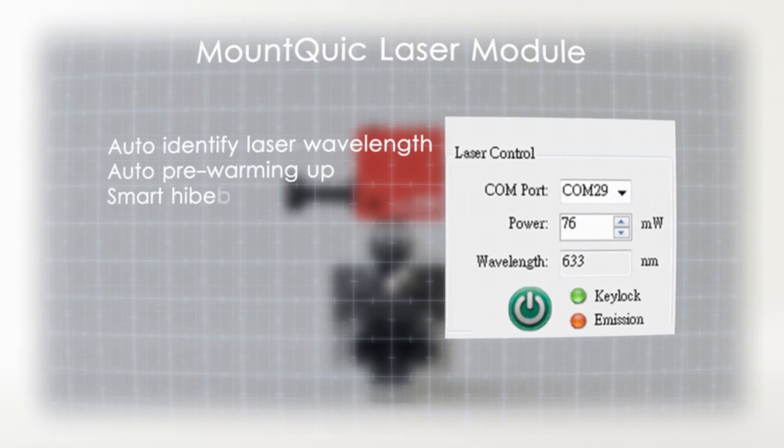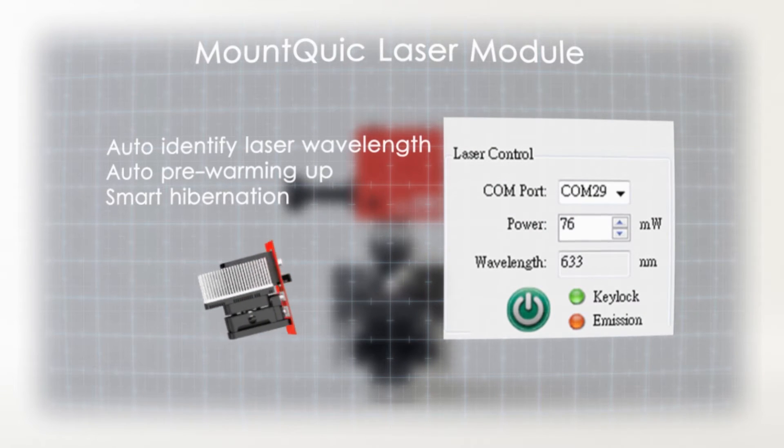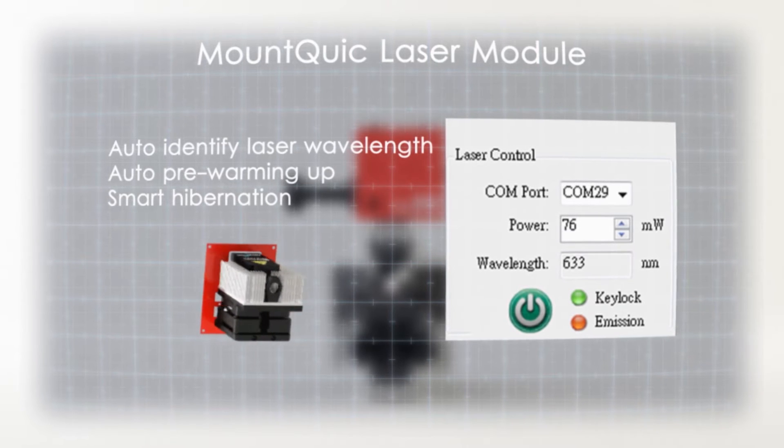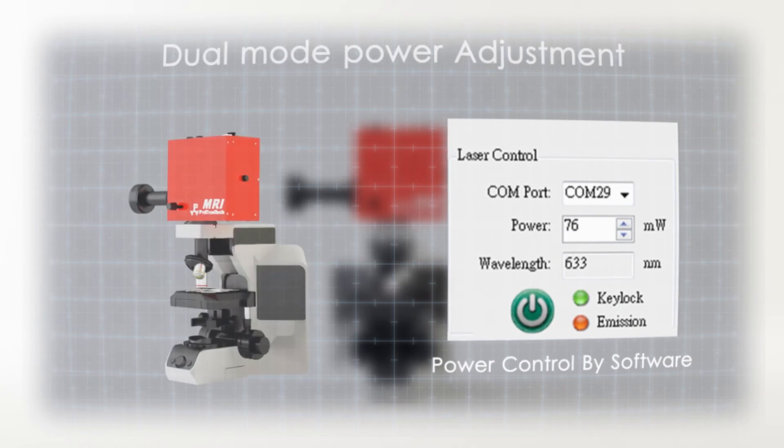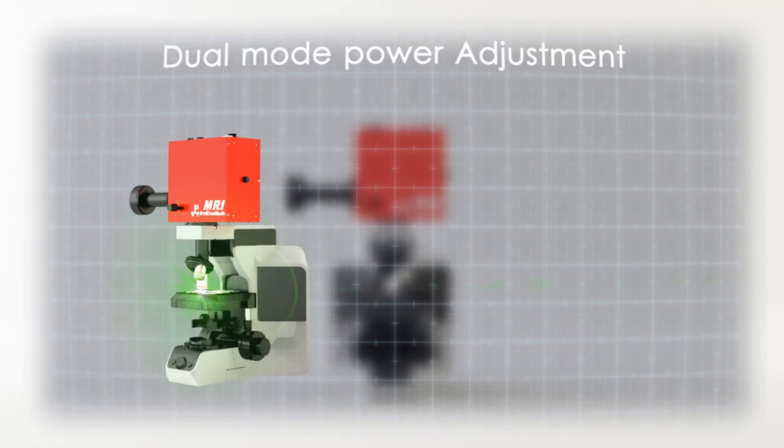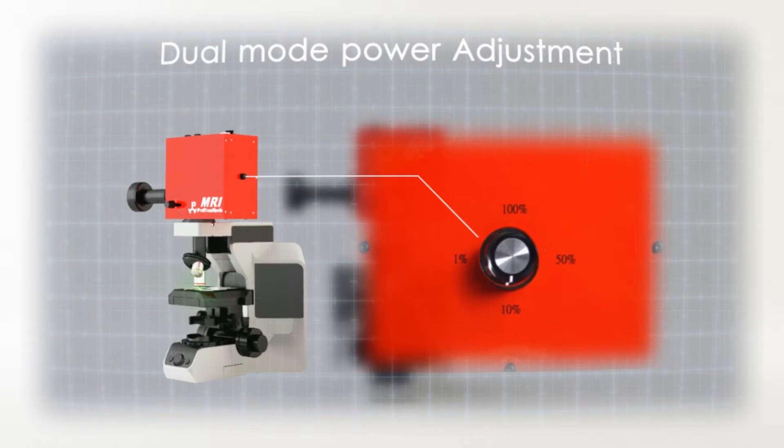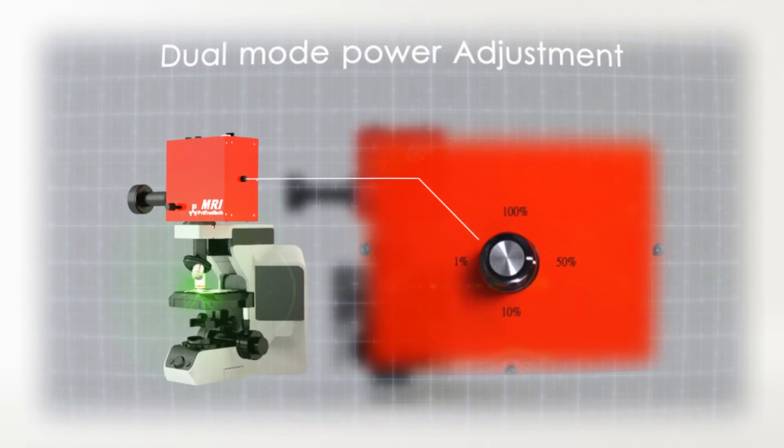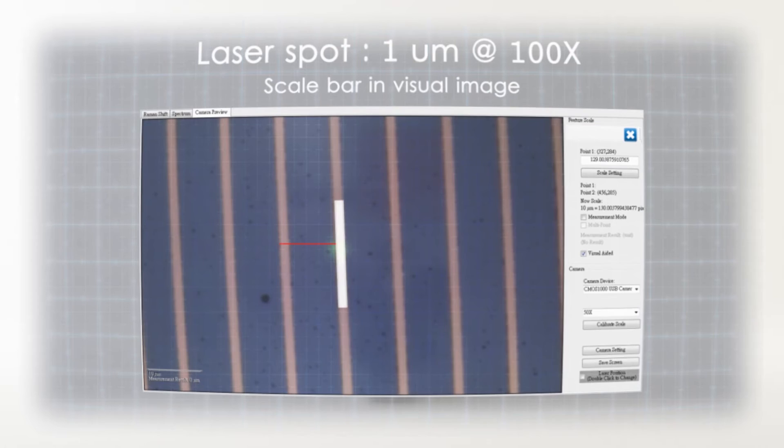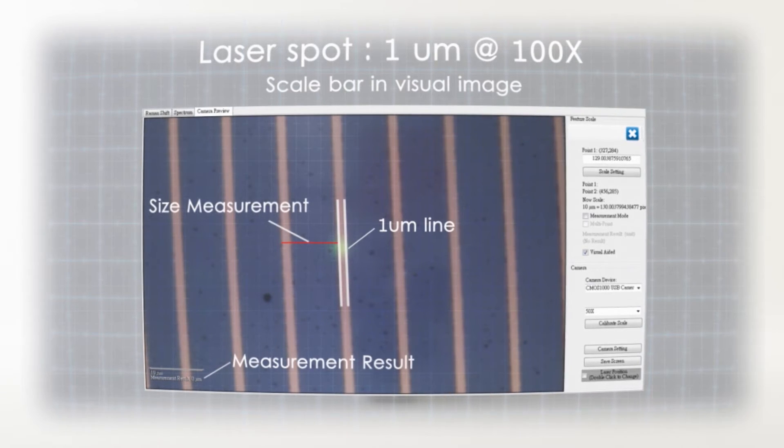MRI software can automatically recognize the wavelength of the current laser in use and can automatically warm up laser or put it into hibernation to increase the service lifespan of the laser. In addition, MRI allows you to set the laser power directly from the software, and the percentage can also be adjusted through rotating the ND filter.